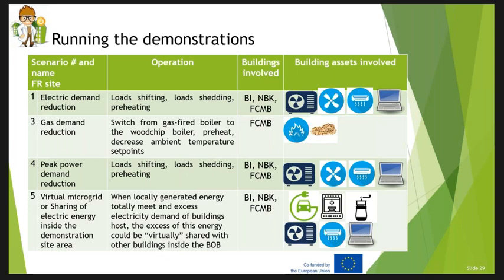And scenario 5, named virtual microgrid or sharing of electric energy inside the demonstration site area, has been triggered by the excess of energy produced on the BI building. So when locally generated energy totally meets the electricity demand of the BI building, the excess of energy has been virtually shared with the other 2 buildings of the block of buildings. And the idea of this scenario was to absorb this excess of energy, to better match building consumption to local PV energy generation. And so the assets participating here were electric vehicles, some big loads of the buildings, and also heat pumps and ventilation assets.